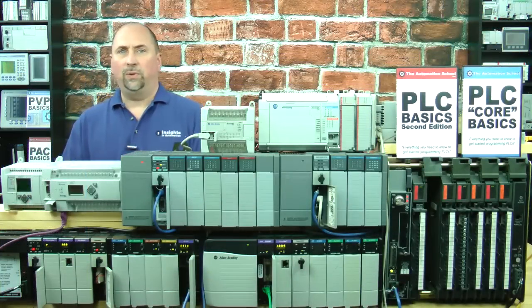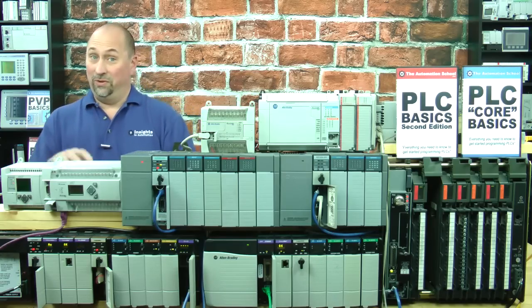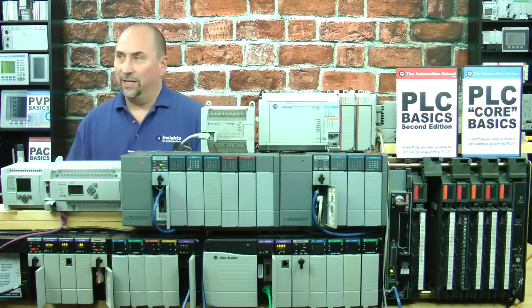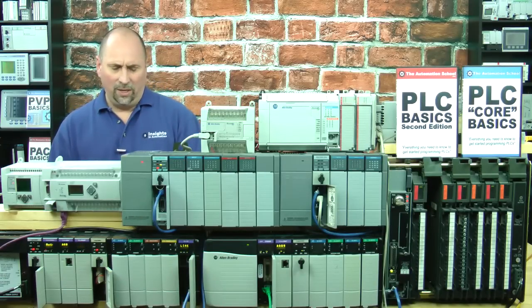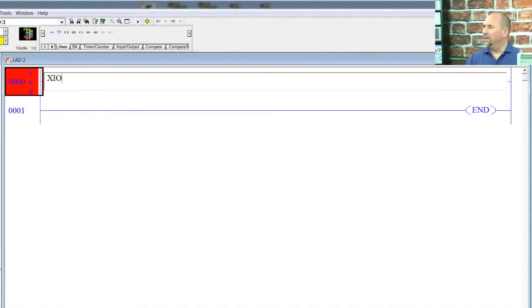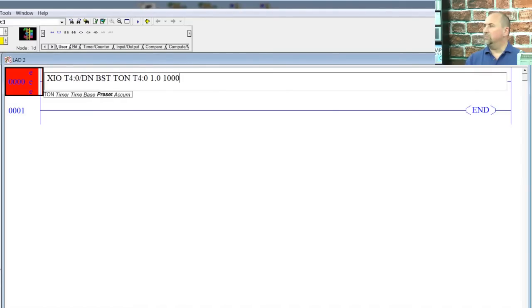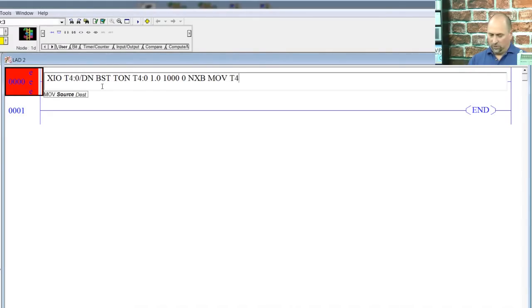Here I'm going to write some sample code to test out our outputs. This is not intended to teach you how to write ladder logic — that's what my courses are for. But let me quickly put together some sample code to test the outputs on this MicroLogix. I'm going to start by putting in an XIO using T4:0/DN, then start a branch and put a TON in there using T4:0 with a one-second time base, 1000 preset, zero accumulate. Then we'll go to the next branch and put in a move, end the branch and press enter.